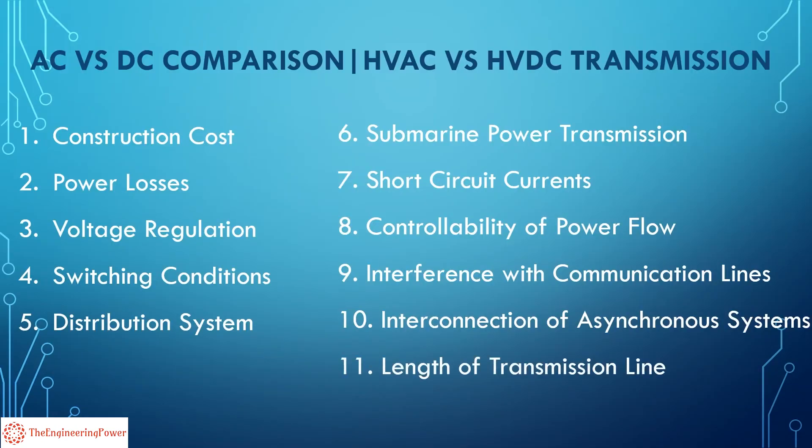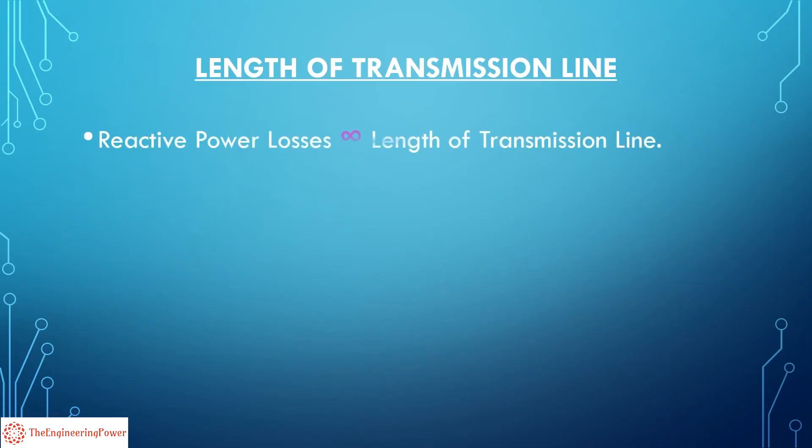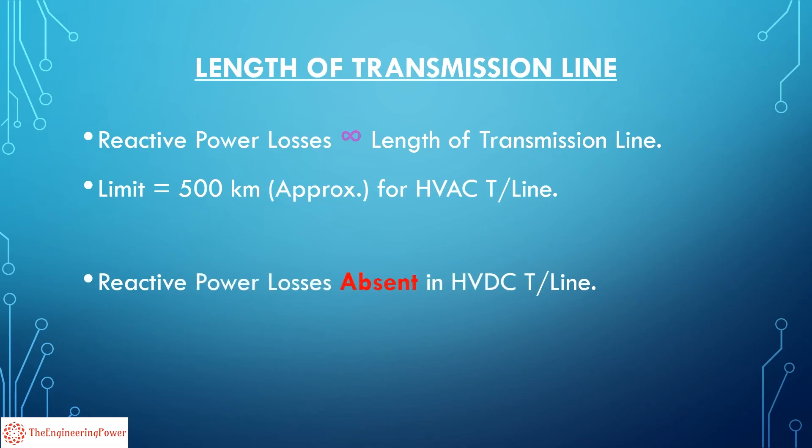Length of transmission line. We know that reactive power losses in a transmission line are directly related to the length of transmission line. Due to this reason, the length of HVAC transmission lines cannot be increased beyond a certain limit as reactive power losses will be too much high. This limit is generally around 500 km. On the other hand, due to the absence of inductance and capacitance, reactive power losses are absent in HVDC transmission line. That's why there is no limitation on length of HVDC transmission lines.